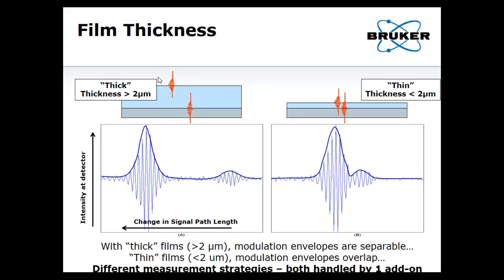We have to make a distinction between films that are optically thick and films that are optically thin. That break is the coherence length of the light source, about two microns. For a thick film, it's a fairly easy direct measurement. A camera pixel watching this would first see modulation from the top surface, then modulation from the bottom surface. Because that film is thicker than the coherence length, you can pretty easily segment these through. However, if you have a thin film, the two envelopes overlap and interfere, so we have to do an indirect model-based measurement using a fitting algorithm.